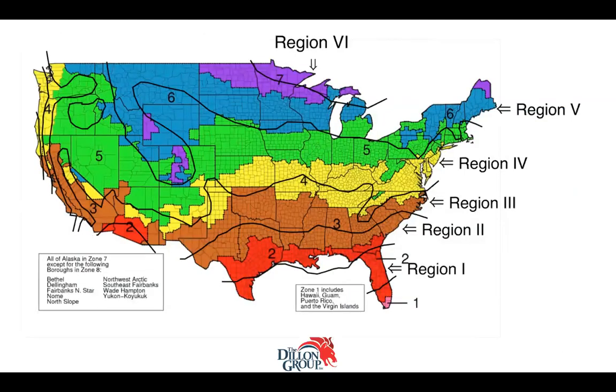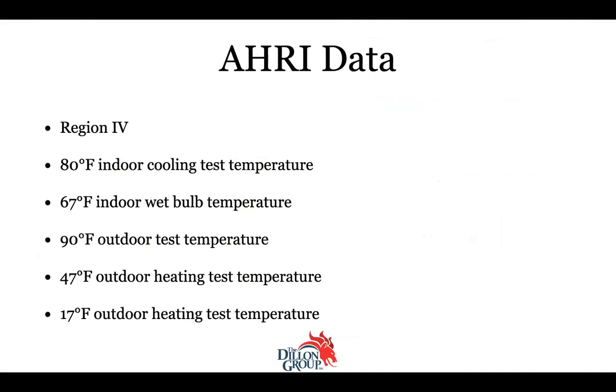I've overlaid the AHRI region map with the code map. And you can see they do not line up. Not even close. There doesn't seem to be any rhyme or reason to the AHRI region map, but that's what it looks like. Wow. And then we have this. The AHRI data that is published, that's on those certificates, is for Region 4, Washington, D.C.